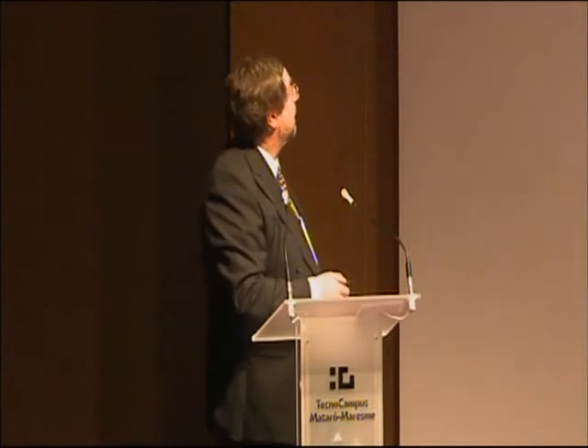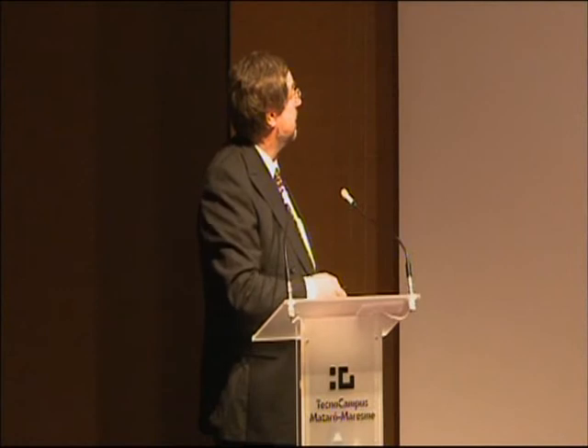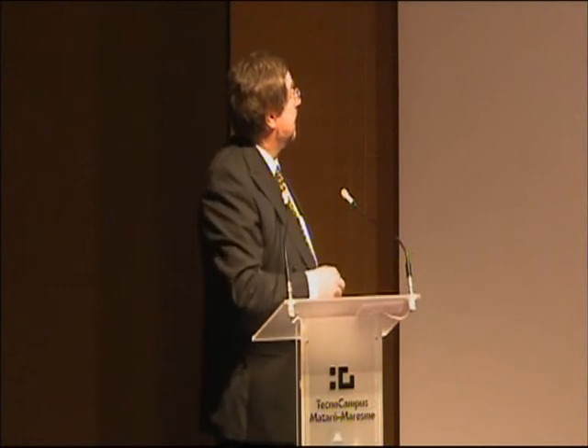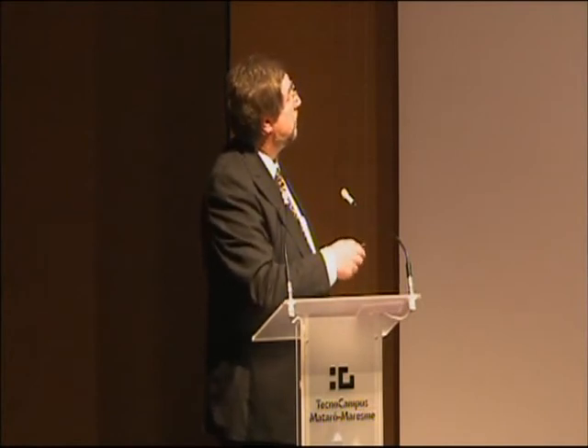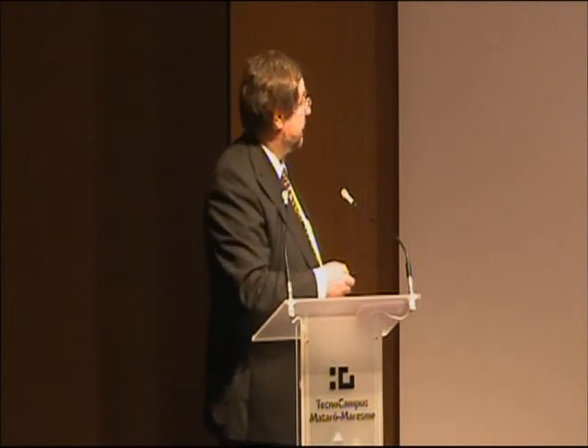The second and last, I think, will be the MHKW Rosenheim. It's a municipal waste incineration plant in Rosenheim. It's in the middle of the town. And the system before was a semi-wet scrubber. This means producing milk of lime and blowing in milk of lime in a spray sorption tower, then the baghouse filter and the stack. SNCR with ammonia in the furnace.